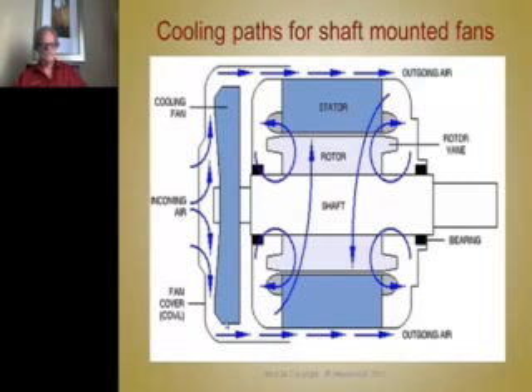Now on the outside, to aid in all that, there's a shaft-mounted fan like the ones I showed in the picture in the last tutorial. And so when the motor spins this centrifugal fan, the air is sucked in here because these rotating blades, see, the air has mass. It doesn't seem like it does, but it does. And so that air is thrown out. When this spins, that air is thrown out to the OD. And so a pressure drop exists here. There's actually a vacuum created inside here because that air has been thrown out, and that gives you a pressure that sucks air in. So the only place for it to go is out.